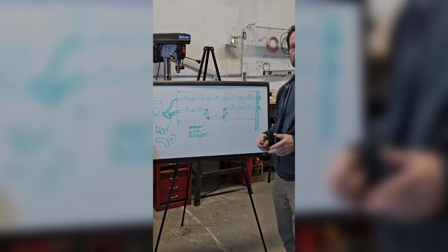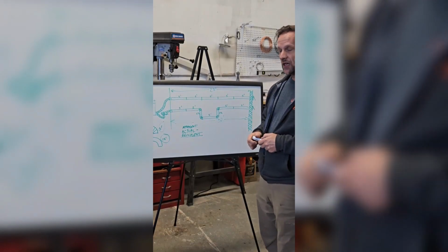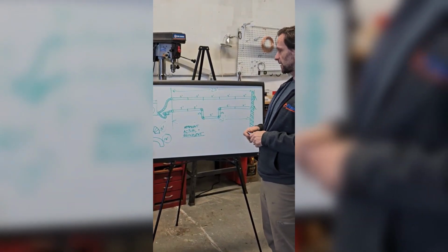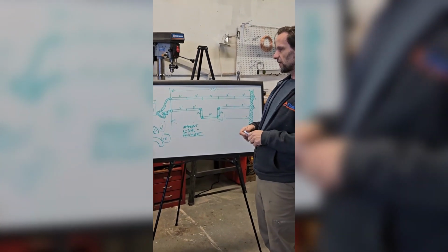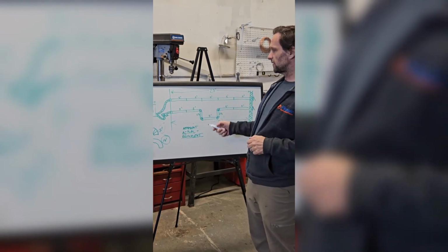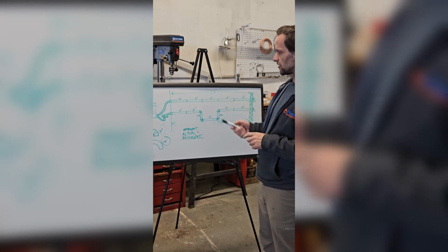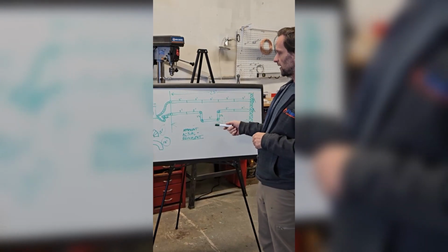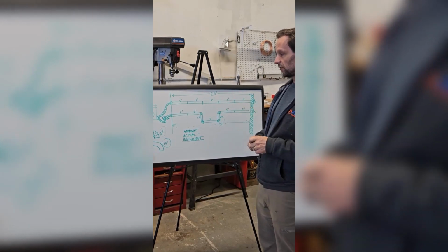It doesn't seem like much, 5 foot, it's not a big deal. Well, actually it is a big deal, and now we'll come to the equivalent length. The equivalent length is the effective length measured by using the straight, least resistant sections of the duct. So each element is translated into a straight, solid run.